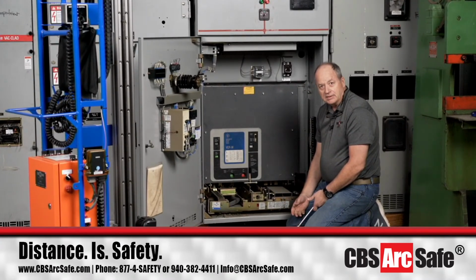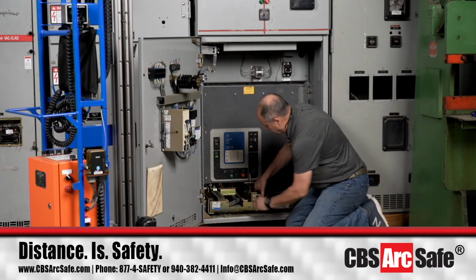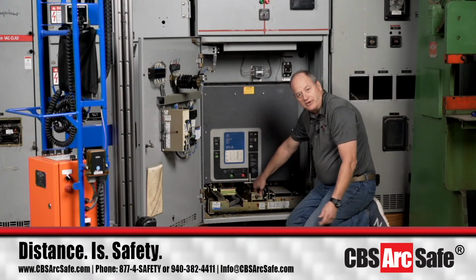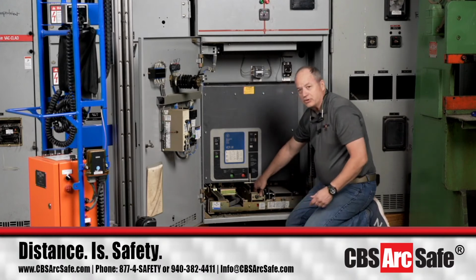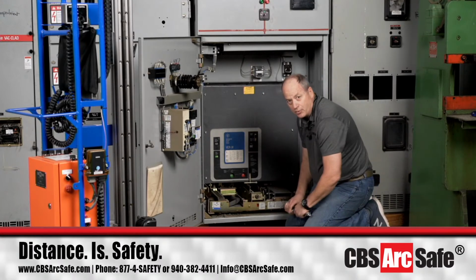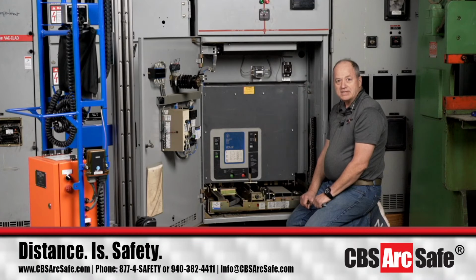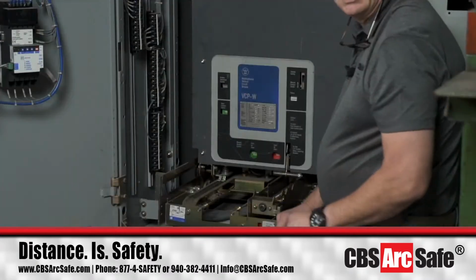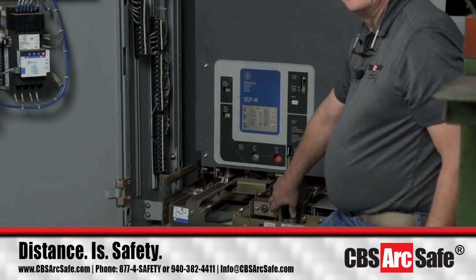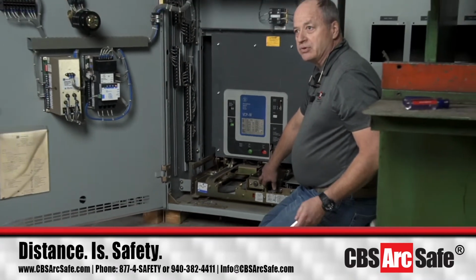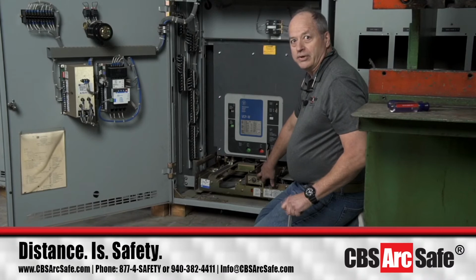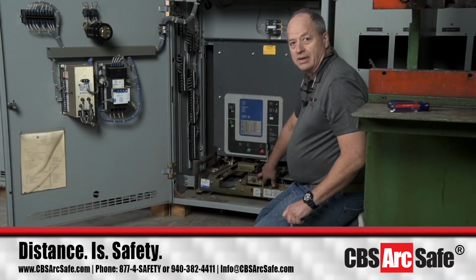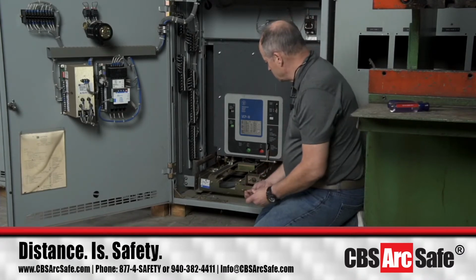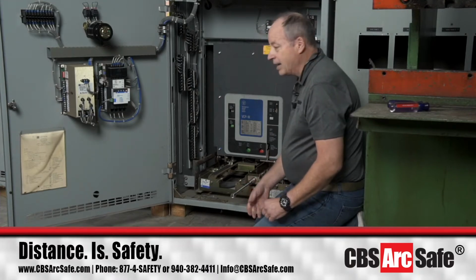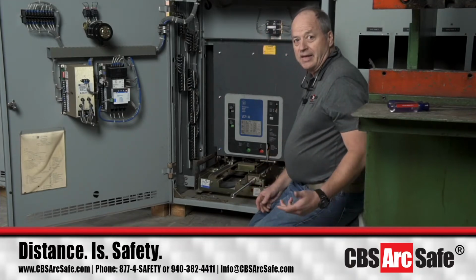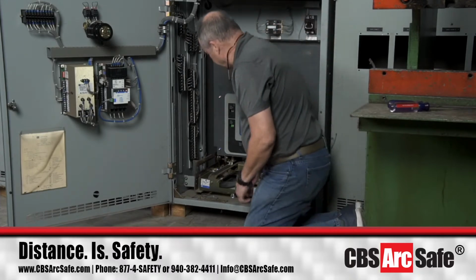Well, Eaton put in a lockout tagout function. So whether you're racking it with the door open or the door closed, if you'll open the door and put the lockout tagout in position, it will easily hold the racking mechanism exposed, so you're not fighting the spring while you're trying to hook up the RRS-1 to rack the breaker out. So now I can just put the tool on here and I can bring the RRS-1 up and then proceed to rack the breaker in and out.